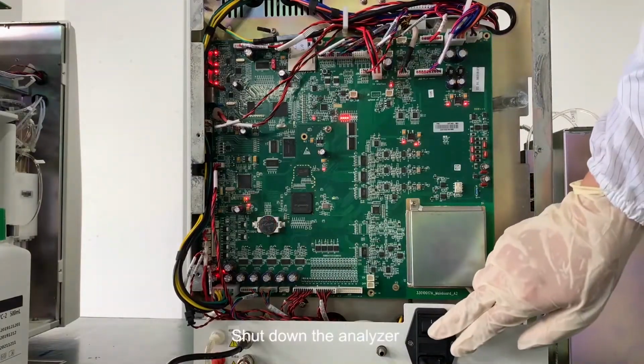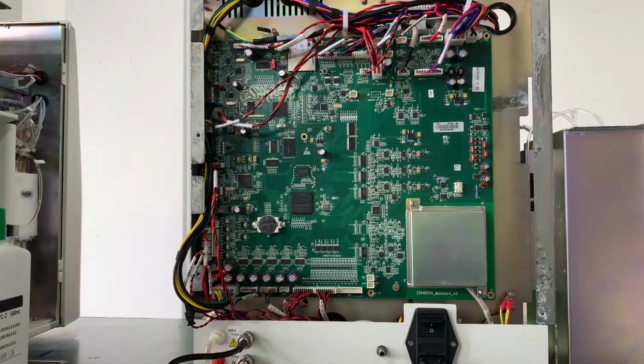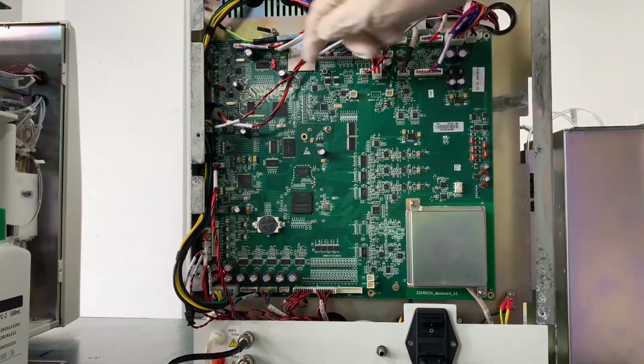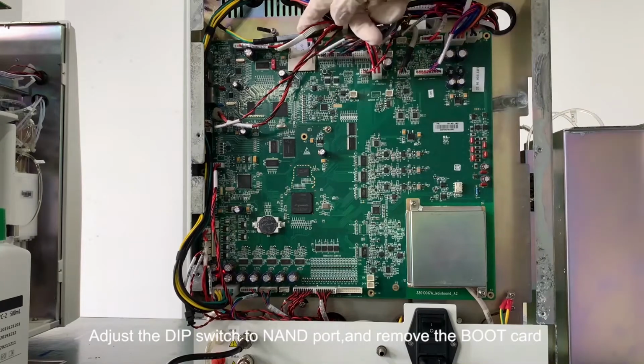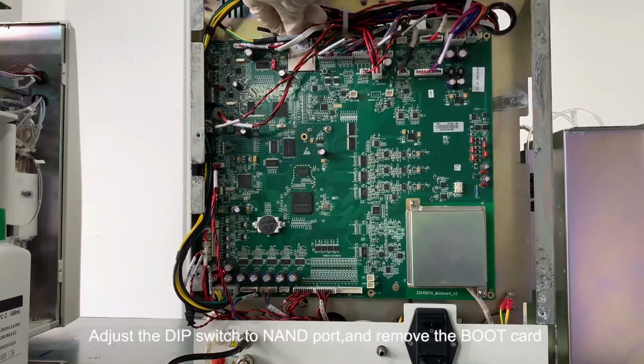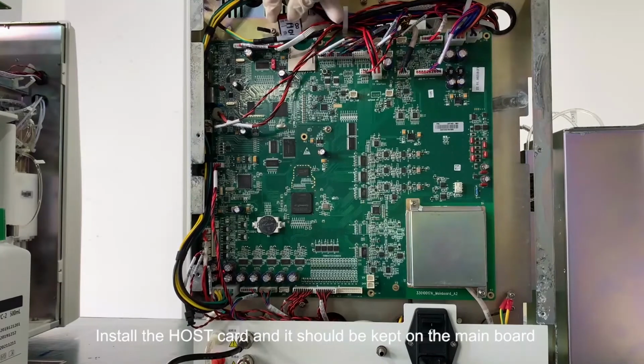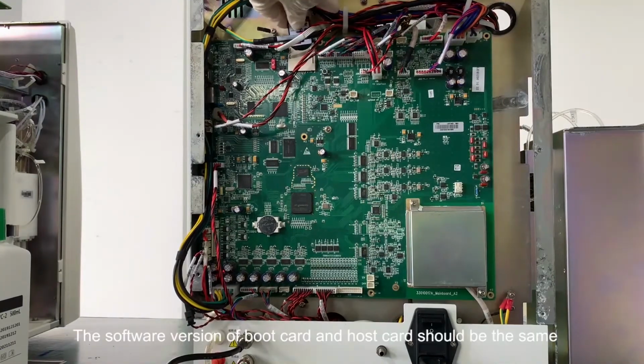Shut down the analyzer. Adjust the DIP switch to the NAND port and remove the boot card. Install the host card and it should be kept on the main board. The software version of the boot card and host card should be the same.